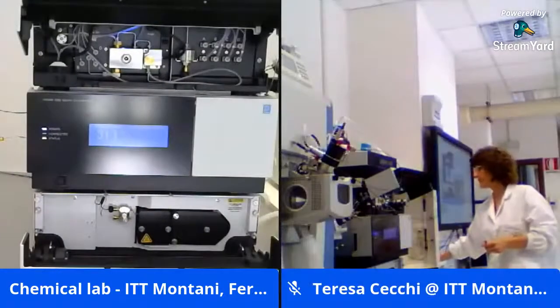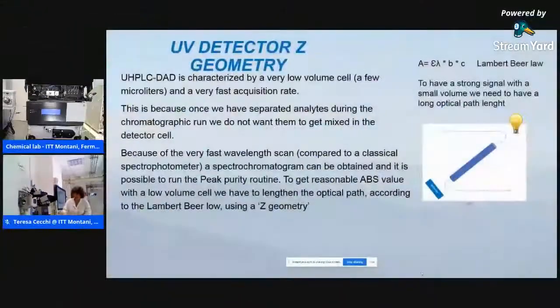Well, the geometry of the cell inside the diode array detector is a Z geometry because we need to keep the optical path quite long, because if the optical path were reduced, the absorbance, according to the Lambert-Beer law, would not be enough. For this reason, to keep the volume very small, but the optical path quite long, we use a Z geometry.